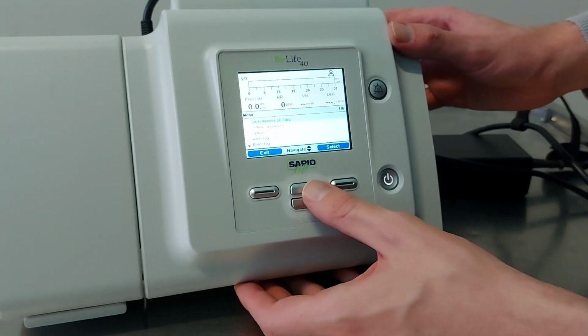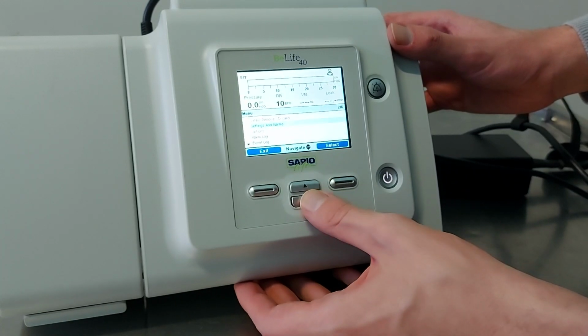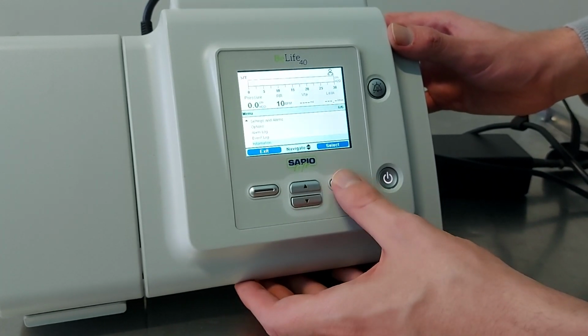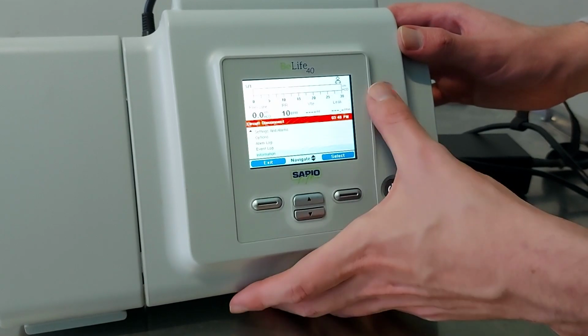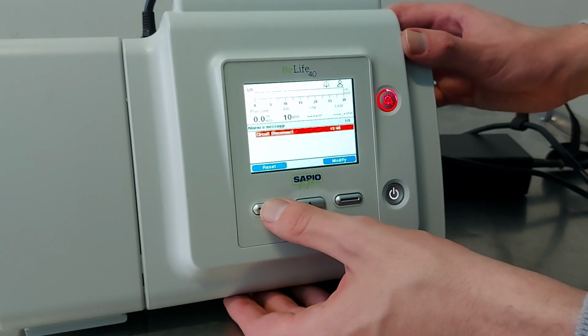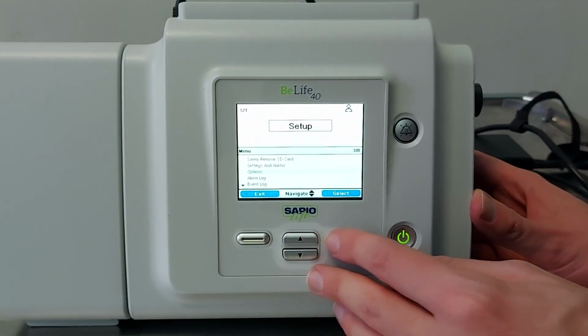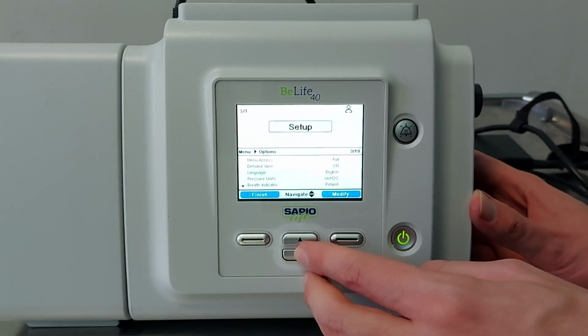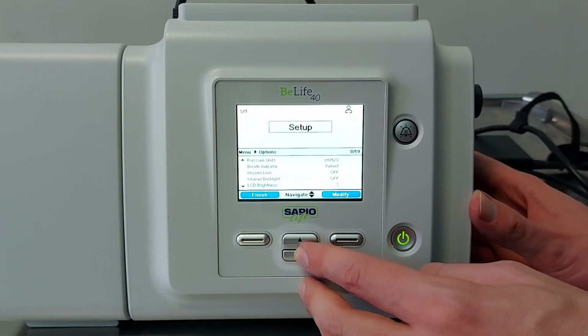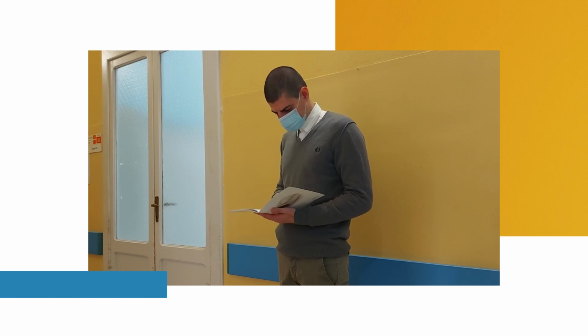Review the user or service manual and confirm the operation of all lights, indicators, meters, gauges, audible signals, and visual displays. The first time a machine is turned on, it may ask for you to set the time on the machine. Different models have different ways of performing the performance tests. Some units have a self-test mode. Run the test based on the manual.